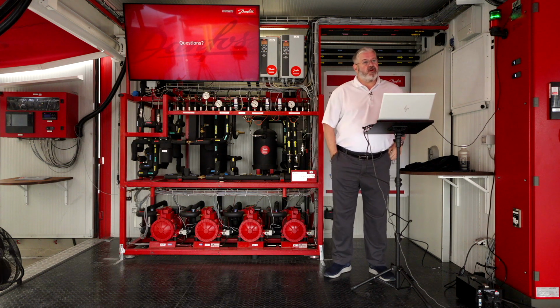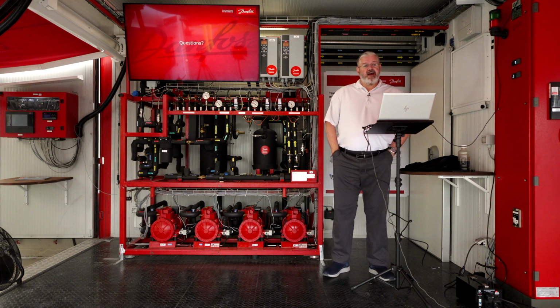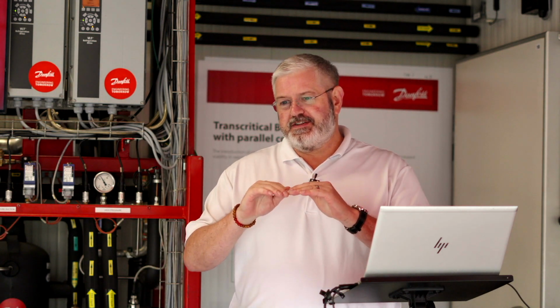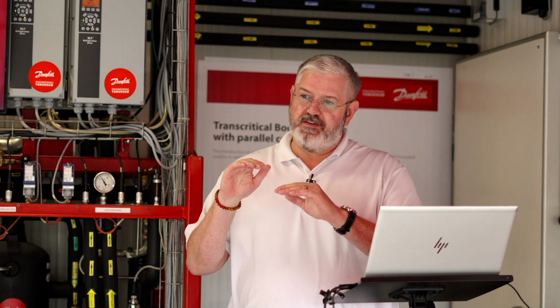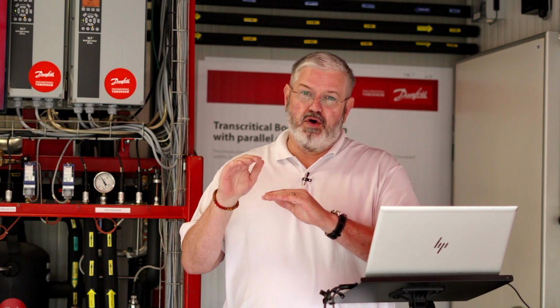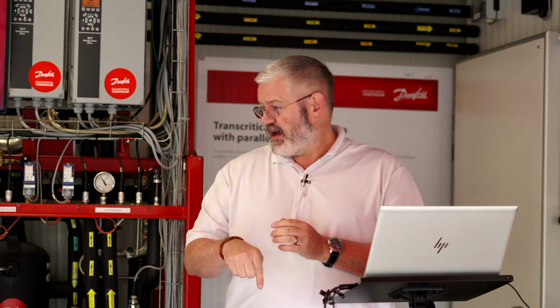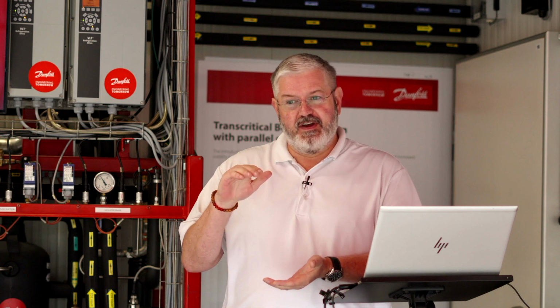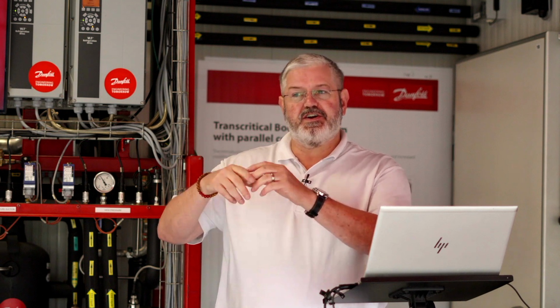Why is a stepper valve required before the flash tank? So the valve before the flash tank, we call that the high pressure valve. If you look at the refrigeration cycle on a pH diagram, when you're above 87 degrees, you're in what's called a supercritical fluid region. That can't change state anymore. You can't boil it or condense it to do work with it in latent heat. So we go across that high pressure valve. It's really like an expansion valve to reduce us down to flash tank pressure, which during that process flashes off some gas while cooling down the remaining refrigerant to have a supply of liquid in the flash tank.